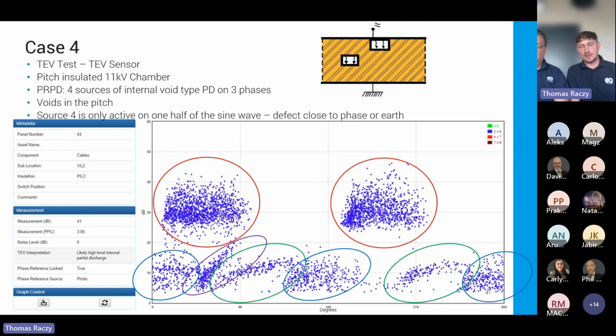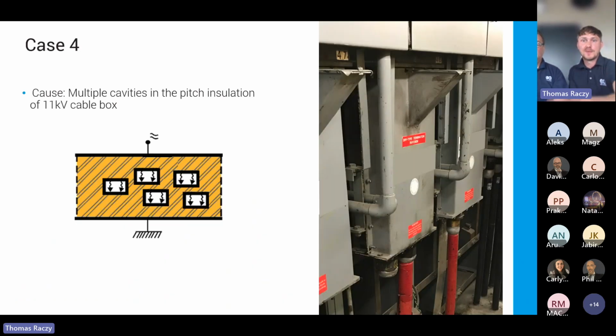slide screen. And the reason we managed to capture that so clearly with so much detail is because the phase reference was correct, and the instrument was triggering correctly off the mains frequency. If there had been any drift to the left or right, that data could look completely different, and we probably wouldn't be able to pick up that many details from this measurement. So that again originated within an 11 kV pitch insulation cable box, so solid insulation.